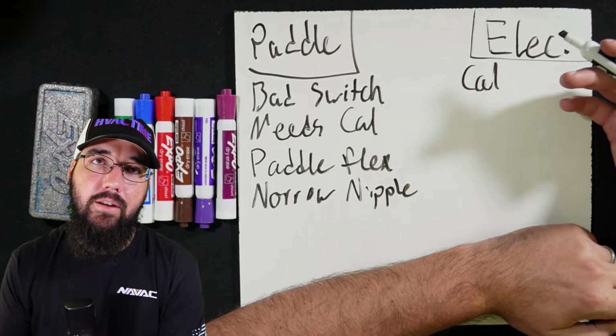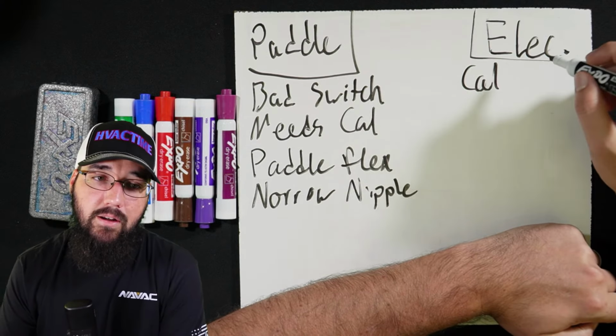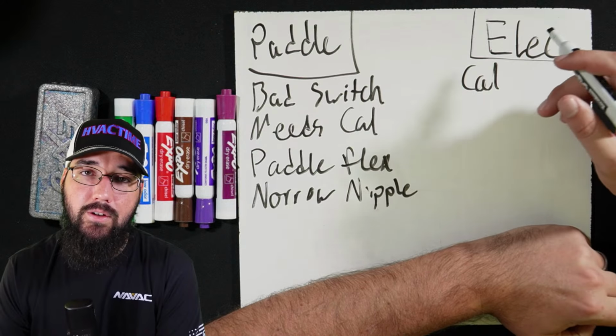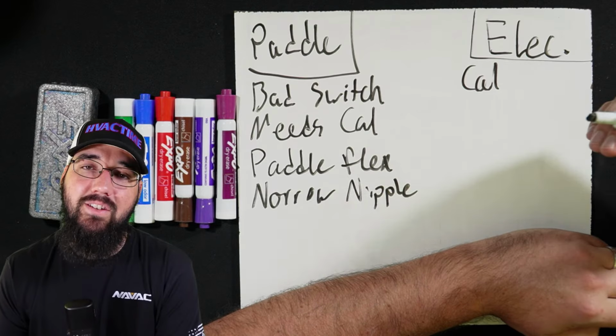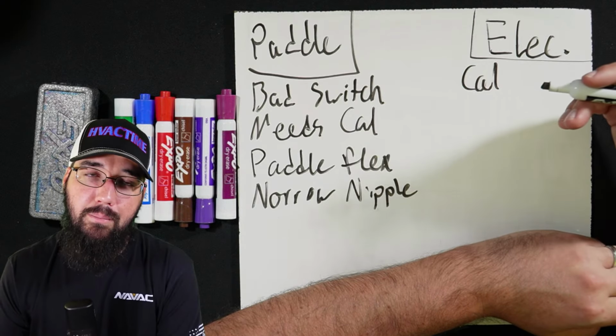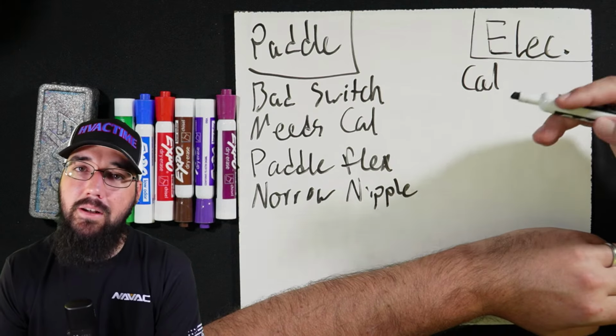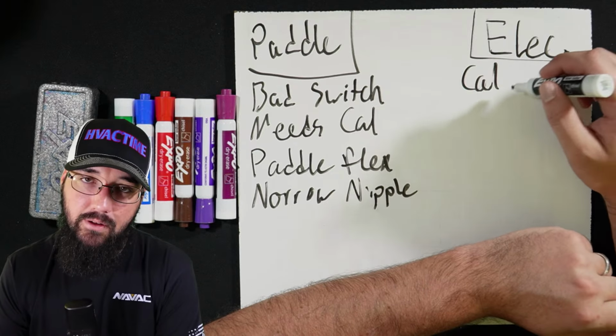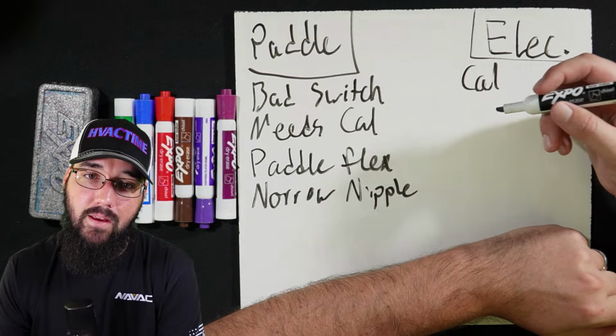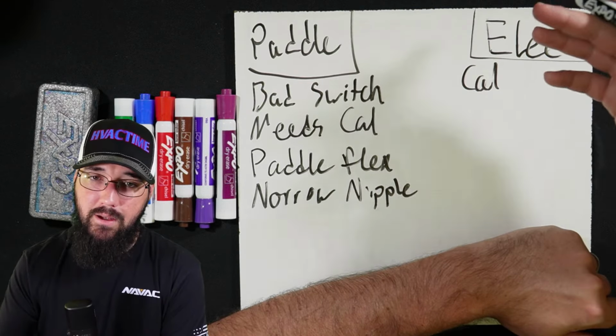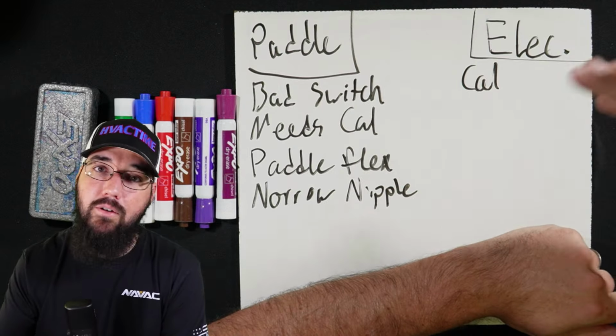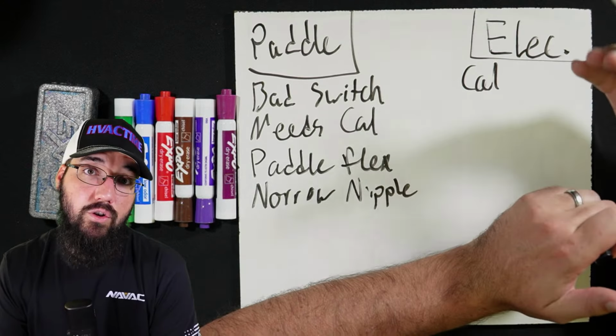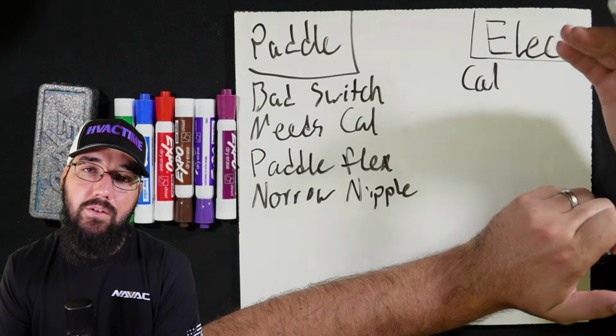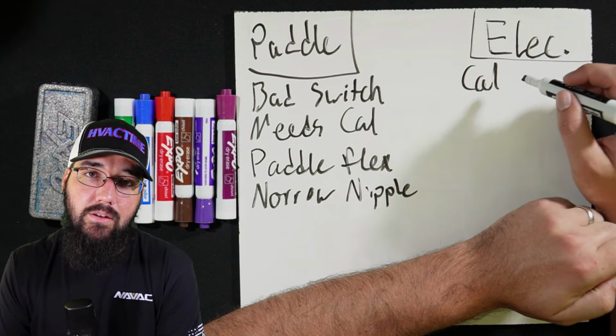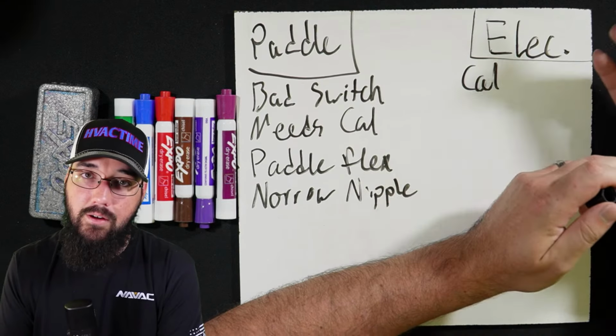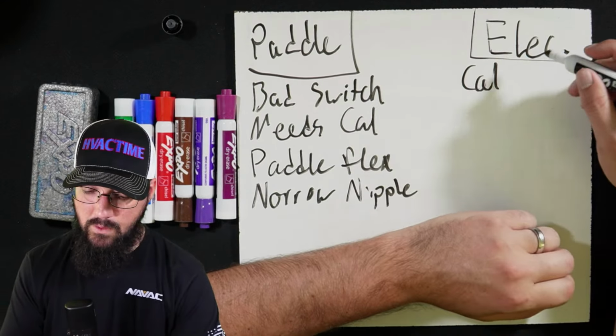And these are recommended to be calibrated to the minimum flow. So you're going to intentionally put the chiller down to its minimum flow allowed, and you're going to set the flow sensor's trip at that level. Not its maximum, but its trip. So that if we actually get below that point, we trigger the flow sensor. Then anything above that, being electronic, you'll probably have some LED indicators, like you'll get deeper into the green or whatever the case may be. It's just showing that you've got really good strong flow. And then as you have less flow, you're going to see that come down. So when you're calibrating these, it's important to calibrate them correctly. Otherwise, they really don't do you much good, and they're just a useless piece of jewelry for the chiller.